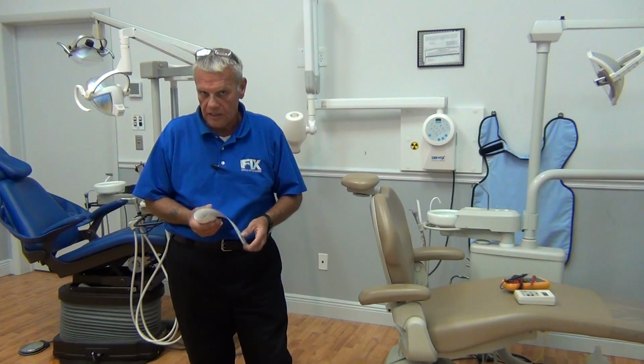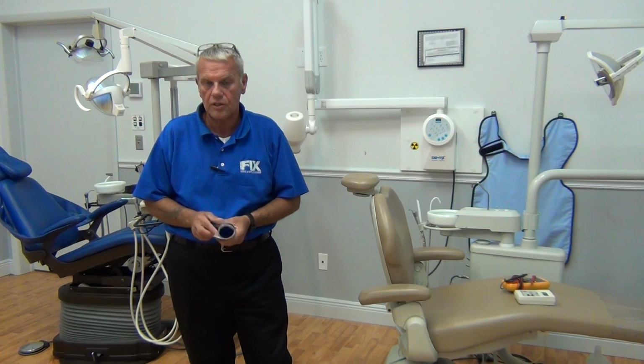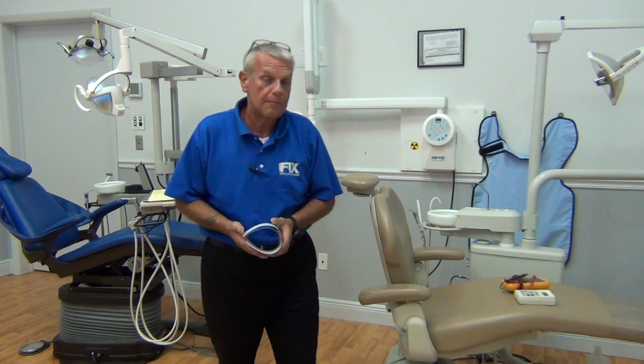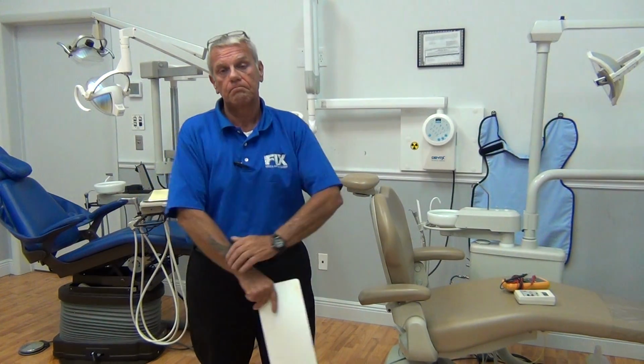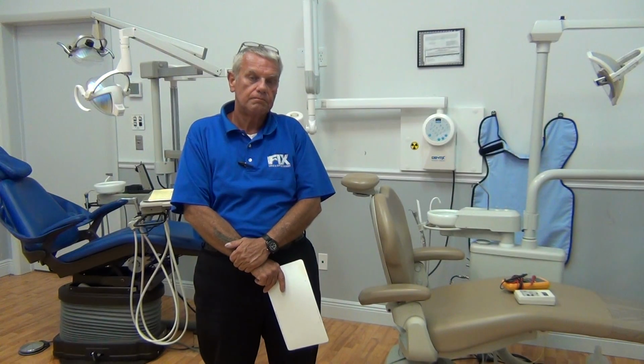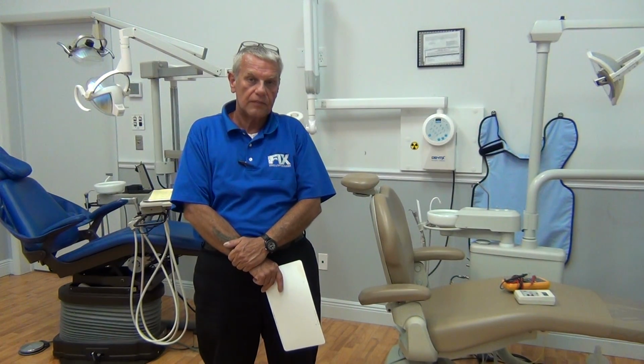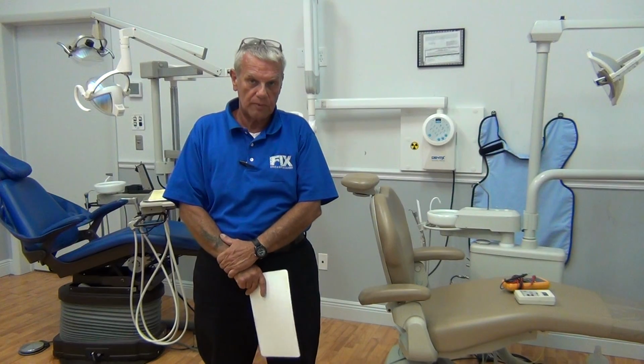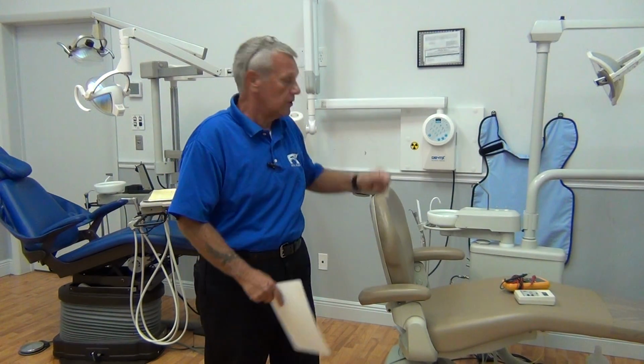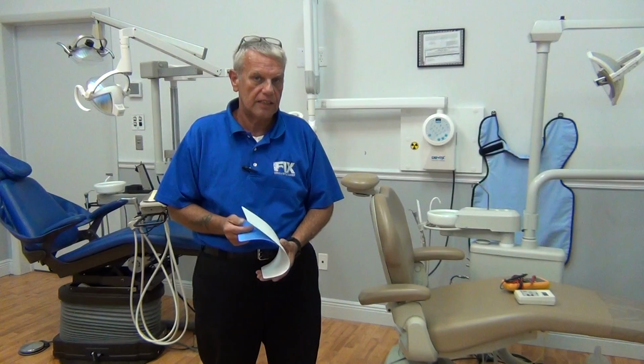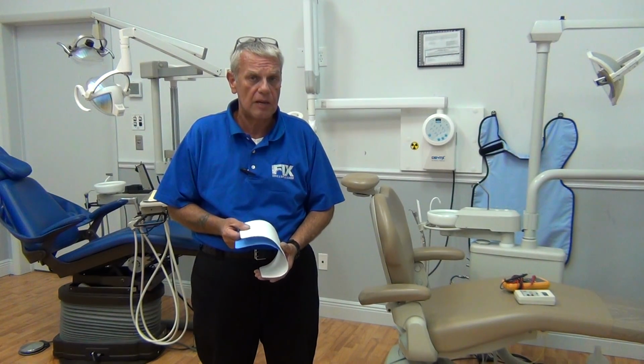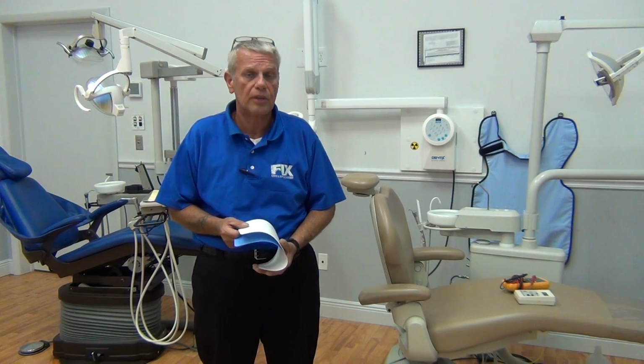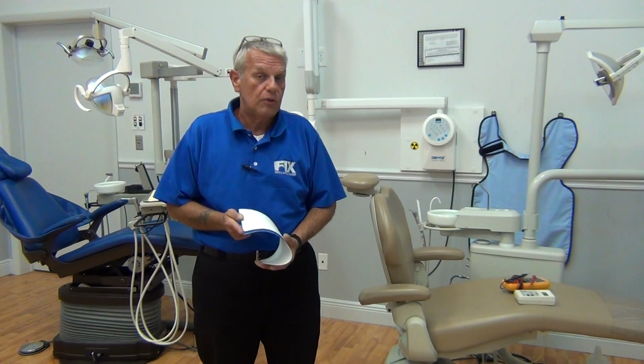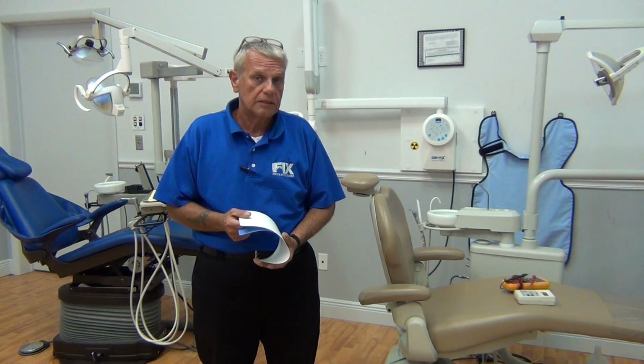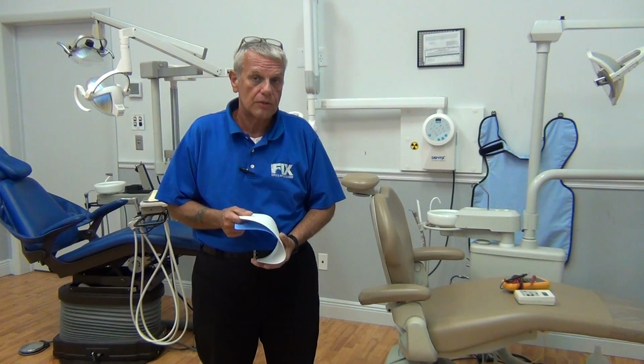Please refer to the FTP site for your individual calibration instructions. Some of your newer machines absolutely have no calibration on them. A Gendex 770, it is what it is. If the calibration's bad, the board must be replaced. Likewise on this one. There are no pots to tweak or anything to calibrate on this x-ray. The KVP and the MA are what they are. It requires board replacement. Before you do that, or before you suggest it to the doctor, please run it past Paul or I first. Check the FTP site, please guys.